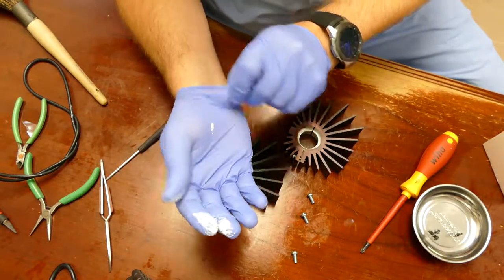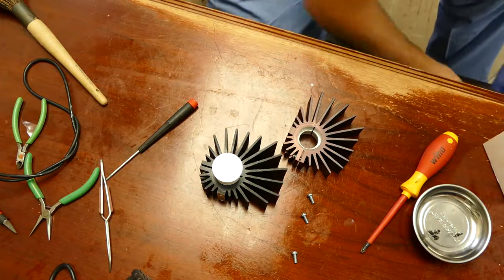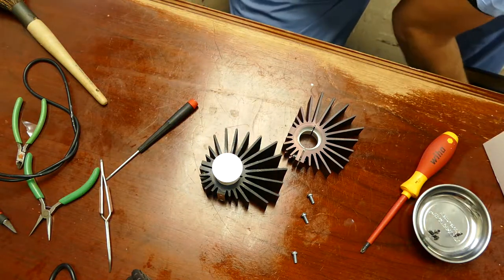And here's the secret: you take your gloved hand and just spin the bulb, and it creates a nice uniform even layer of thermal compound. You're not making a mess. See that? Because all you're trying to do with the thermal compound is create an interface between two materials. So there we go, nice uniform coating. Make sure that the nodule is aligned properly. Put it in its heat sink. Now you can tell I got a dirty glove so I'm going to pop that one off, because you don't want to touch the bulb after you've dirtied up one of your gloves. And I'm going to install a new glove.